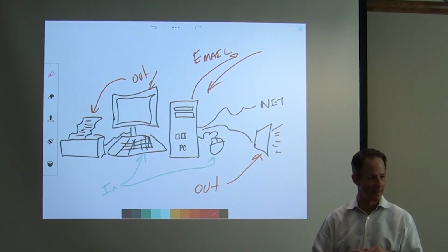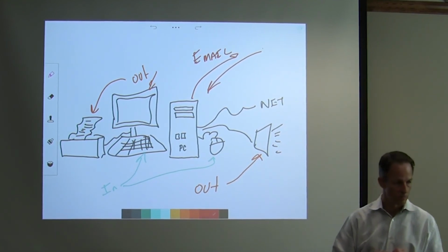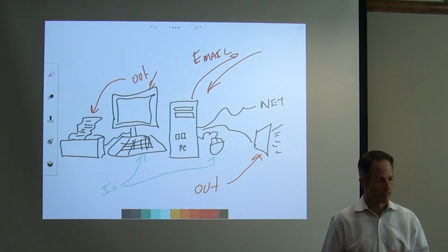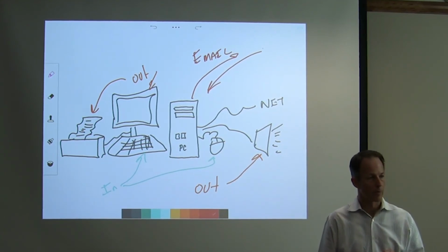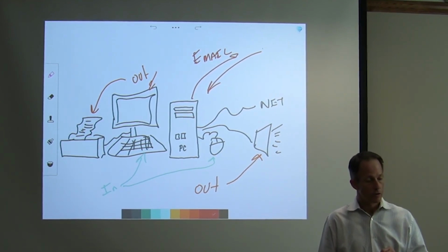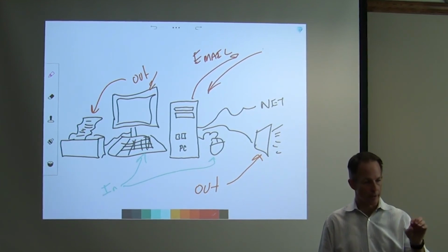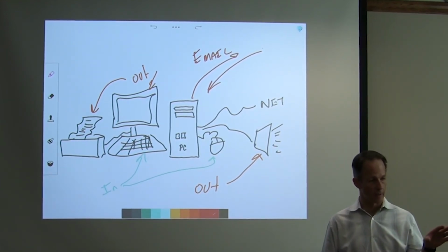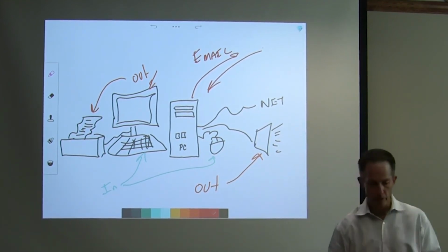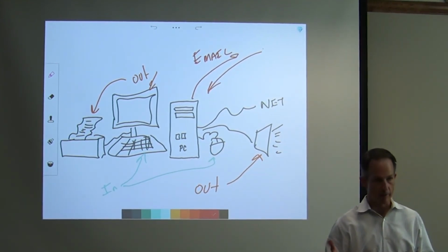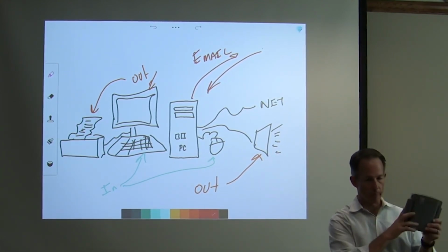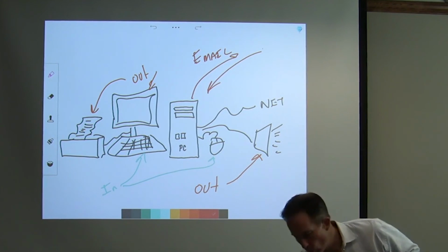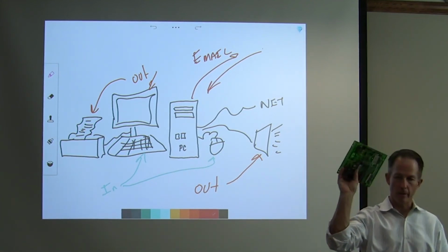I have a question regarding, if I pulled up my building, the Nichols building one time, usually if you have a card that's down or something, it'll be yellow, but the card was actually orange, and I talked to Brooke, and he didn't understand what orange meant. Okay. So the yellow and orange are different status indicators of a particular card. Typically you're going to see yellow-orange come from a Talon type card. We will see yellow occasionally from this, I believe.